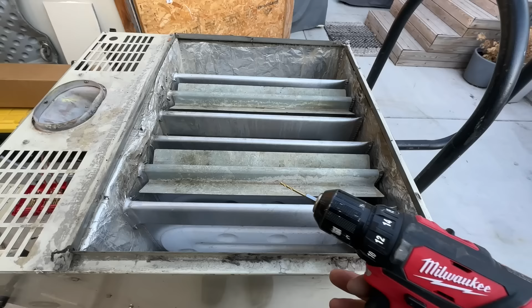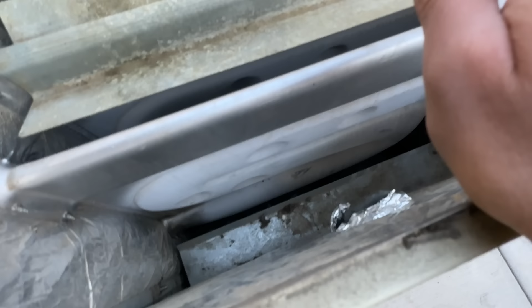Now that we've done our flame test, being as this is a burner furnace, we're going to duplicate a crack or a hole in the heat exchanger in a few various places. A lot of common ones are right here in the middle after the flame has started, so we're going to do one right about here. As you can see, we've got a tiny little hole there. Let's see what happens.